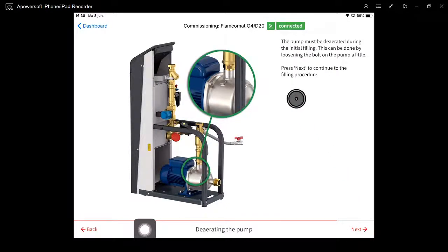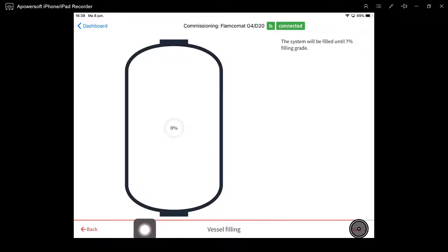Then we will start filling the vessel, and during filling we need to deaerate the pump by loosening the screw on the pump a little bit and letting the air go out. And by pressing next, the pumps will start running to fill the vessel. And I'm now just filling the vessel until it says OK. Successful. Then I press next.